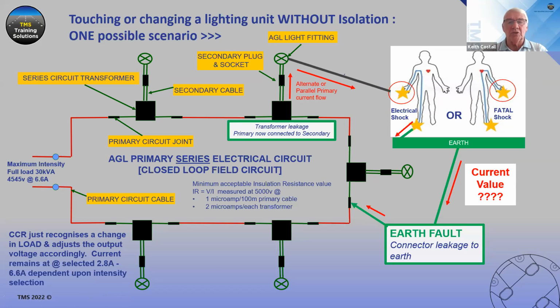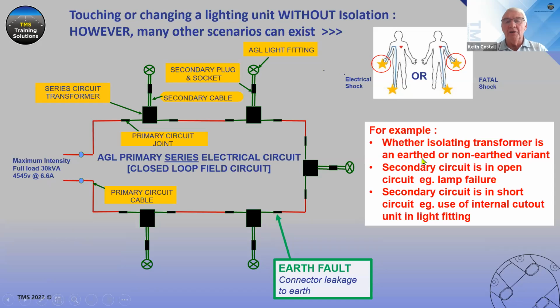There are other scenarios, of course. So this is not exhaustive. There are other issues which can create problems. As for the isolating transformer itself, this transformer that we've got many of out in the field, does it have an earth connection on its output, on its secondary side, or not? Because the two options are available. If there is an earth connection and leakage occurs, there is already an alternative path rather than through the human being. So there are merits in the use of earthed transformers and non-earthed transformers, which can both exist.